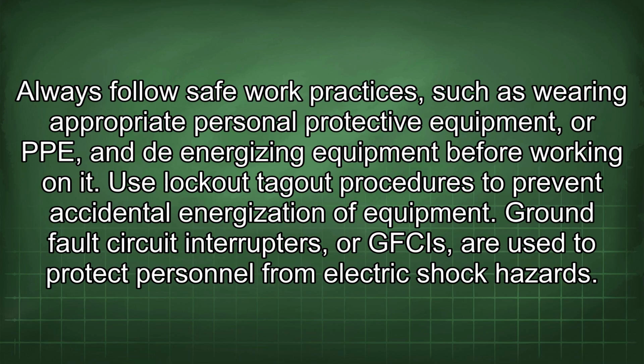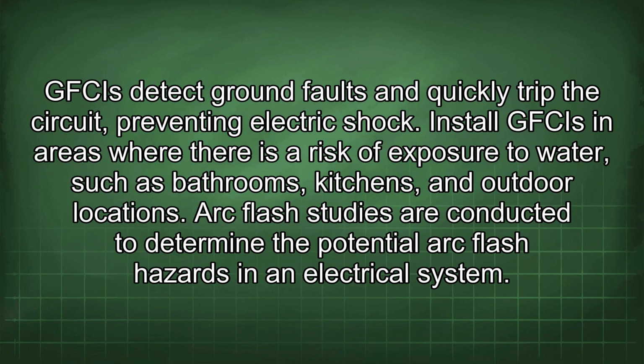Always follow safe work practices such as wearing appropriate personal protective equipment, or PPE, and de-energizing equipment before working on it. Use lockout-tagout procedures to prevent accidental energization of equipment. Ground fault circuit interrupters, or GFCIs, are used to protect personnel from electric shock hazards. GFCIs detect ground faults and quickly trip the circuit, preventing electric shock. Install GFCIs in areas where there is a risk of exposure to water, such as bathrooms, kitchens, and outdoor locations.